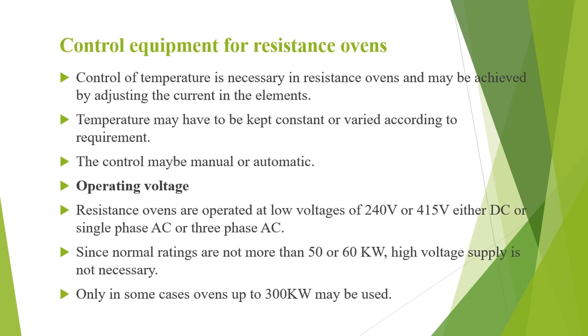Control equipment for resistance ovens — control of temperature is necessary in resistance ovens and is achieved by adjusting the current in the elements, so temperature can be kept constant or varied according to the requirement, either manually or automatically. Operating voltage: resistance ovens operate at low voltages of 240V or 415V, either DC, single phase AC or 3-phase AC supply. Since normal ratings are not more than 50 to 60 kW, high voltage supply is not necessary.